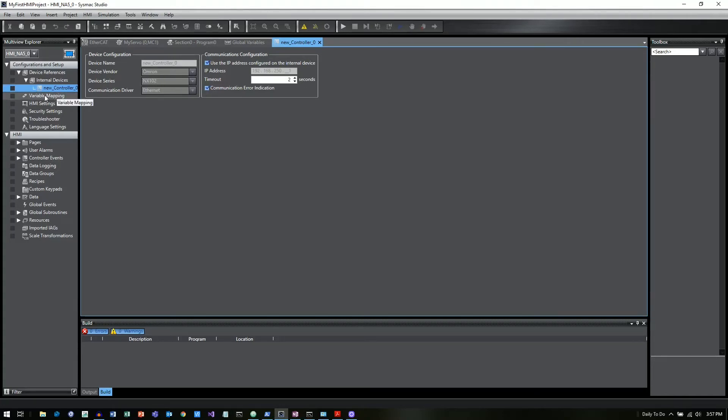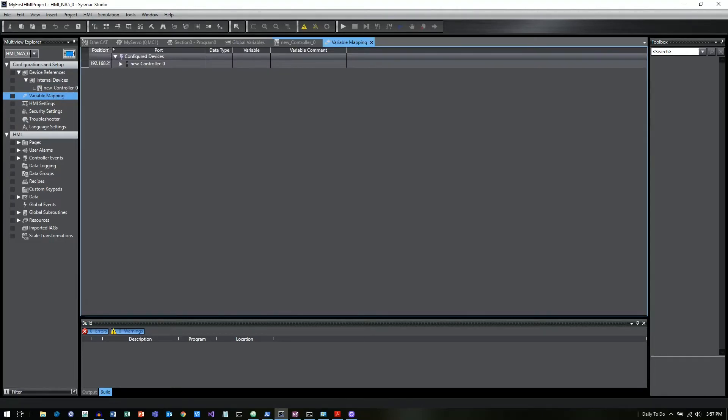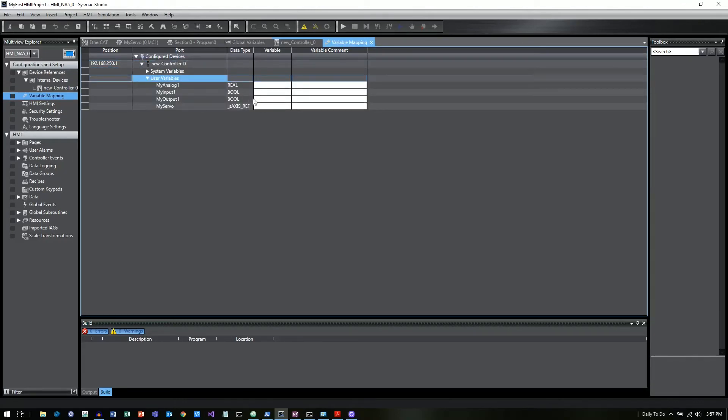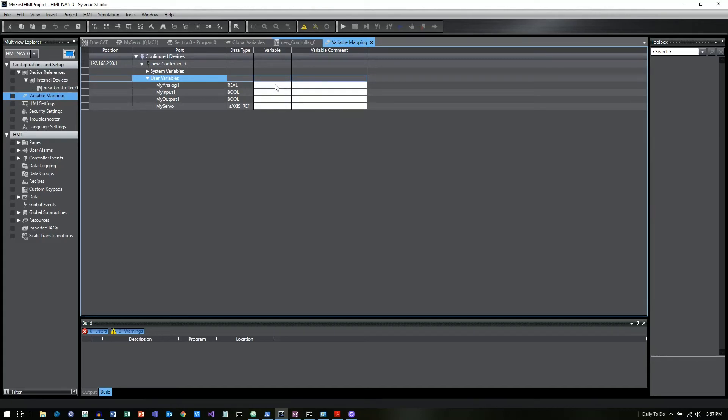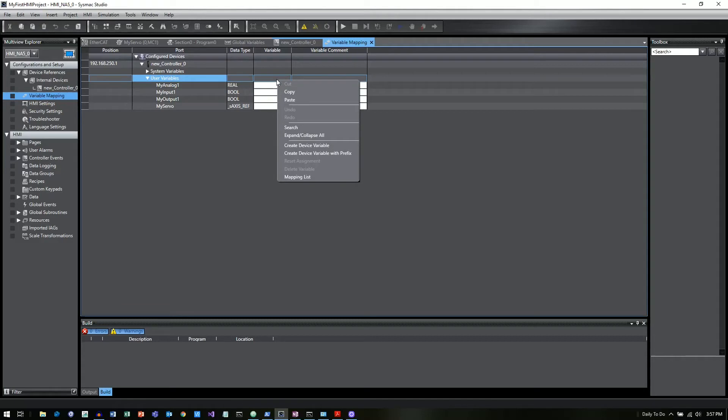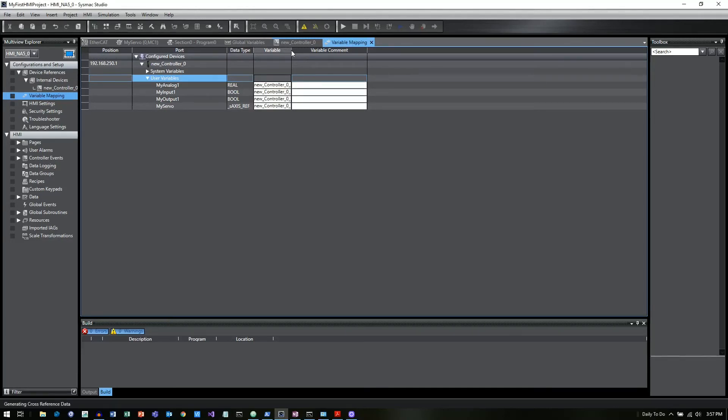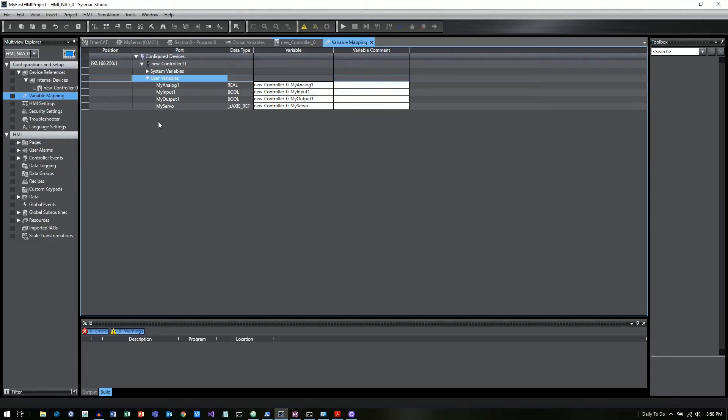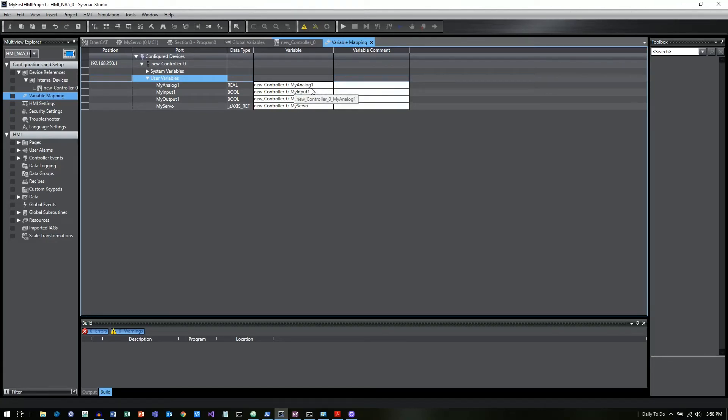What we have to do then is go into Variable Mapping. And we can see now that this IP address is going to be that new underscore controller underscore zero, which is just the default name for our PLC. We can expand that. And then we can see this list of variables for our PLC project. So if we right-click on the user variables, we can say Create Device Variable. And it'll automatically create a device variable. So you'll notice that it basically puts the controller name, underscore, and then the variable name. Now, the reason you have to use two separate variable names, one variable name for your HMI project, and then one variable name for your PLC project, is because there is a chance that you could actually use this HMI to control multiple PLCs. So you could actually have two PLCs that both have the variable myanalog1. So by putting a prefix on there, we can specify what PLC that goes to.